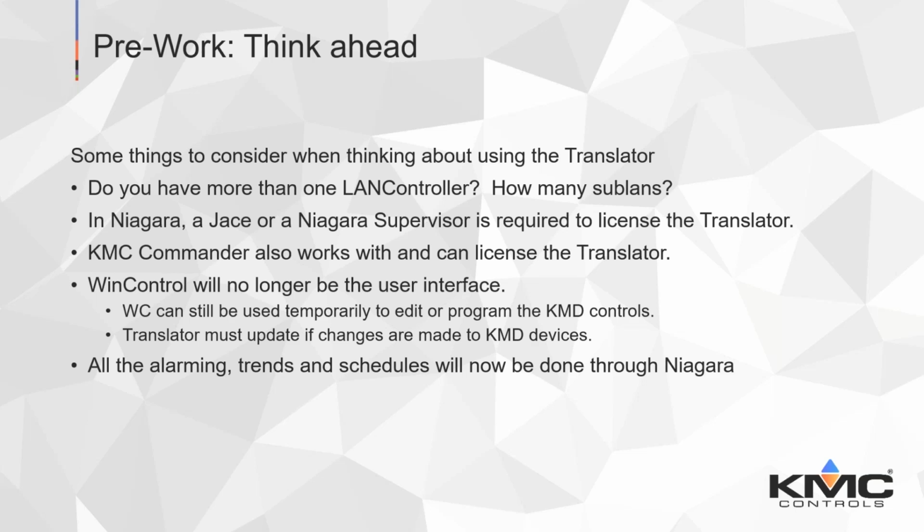Off the cuff, with normal Niagara graphics, I would say it's probably in the 32 range of controllers. Now, maybe you could go 64, like if you had a LAN light, depending on how much data you really wanted to bring in. It's not really a hard and fast rule here, just some guidelines. Yeah, so that's what we're looking at. I would agree with you there.